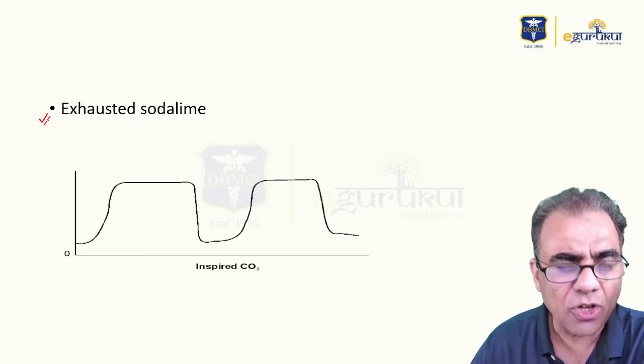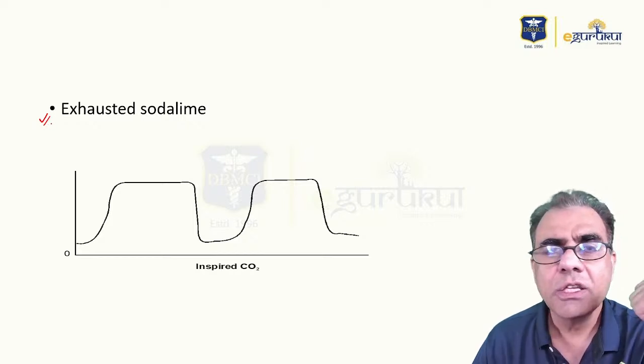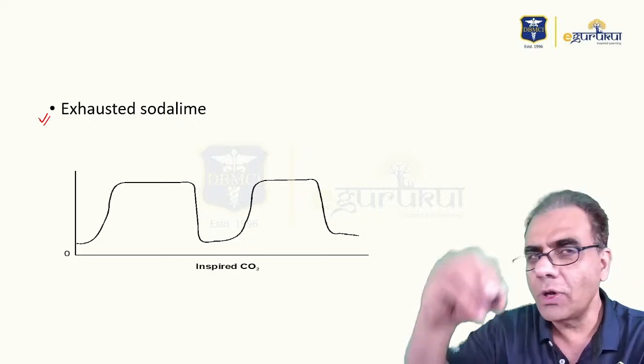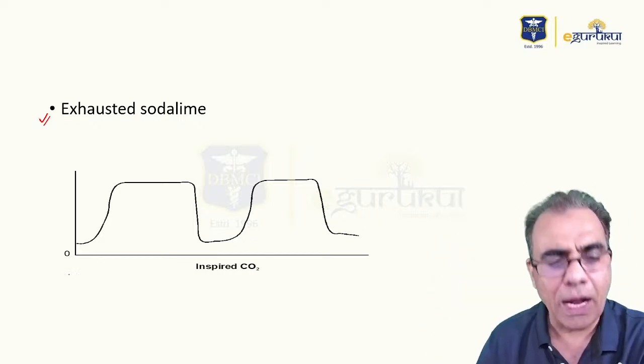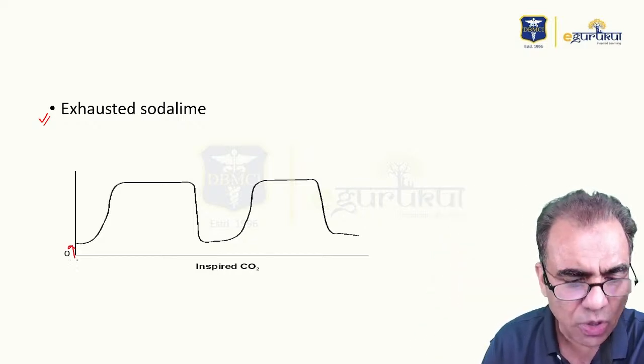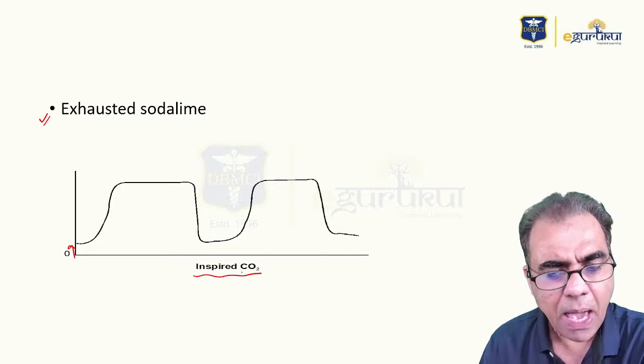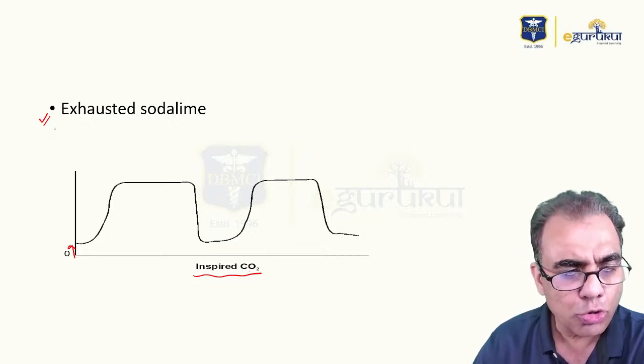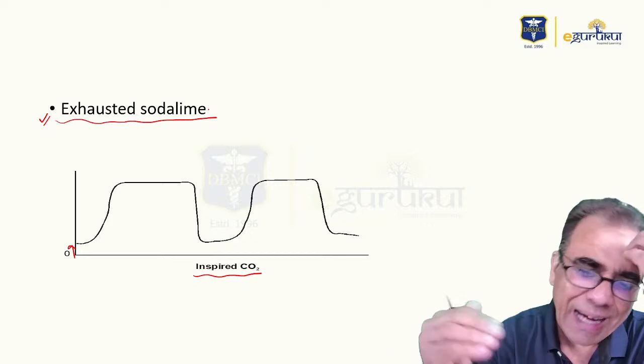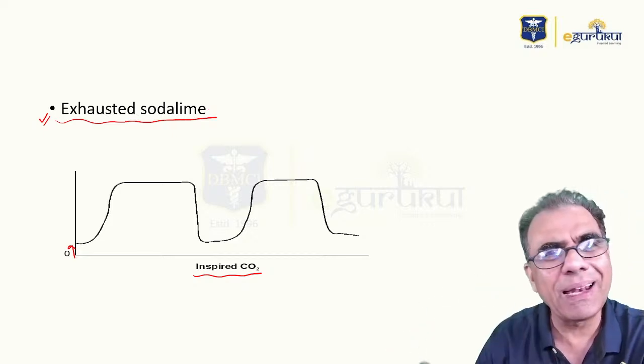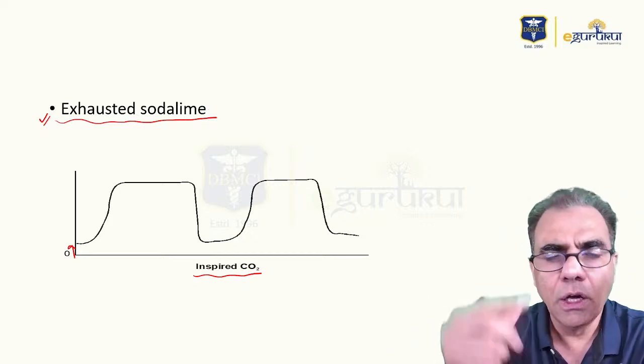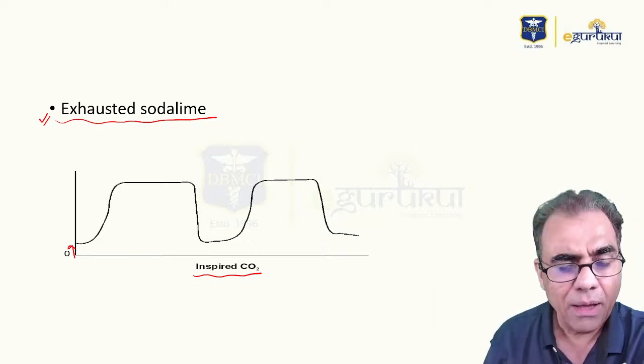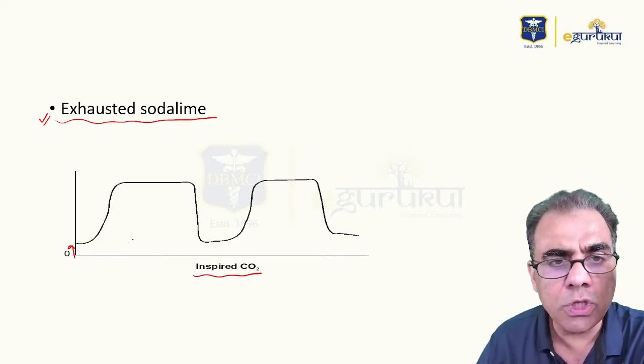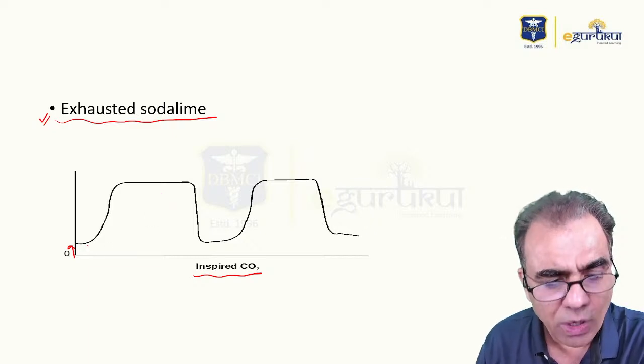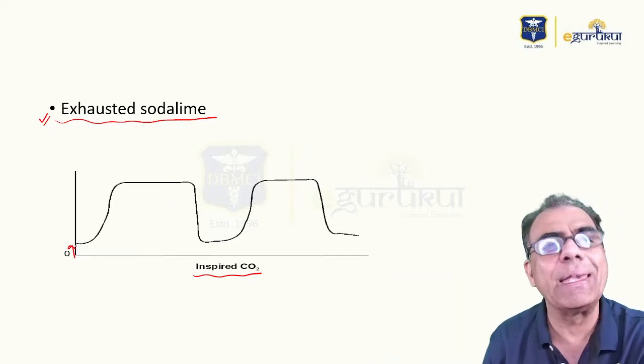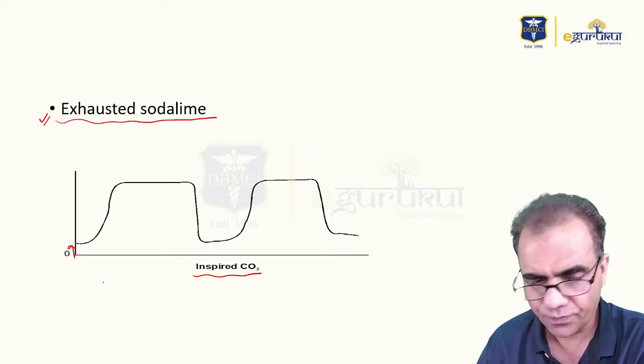Then if soda lime is exhausted, CO2 will not get absorbed. So inspiratory CO2 will come and increase the baseline. So if the baseline is increased, that means the patient is inspiring CO2, so soda lime is exhausted. We can identify exhausted soda lime by the color of the indicator also. Before that, we have already diagnosed exhausted soda lime by looking at the CO2 graph, which has shifted the baseline. It's not coming to zero.